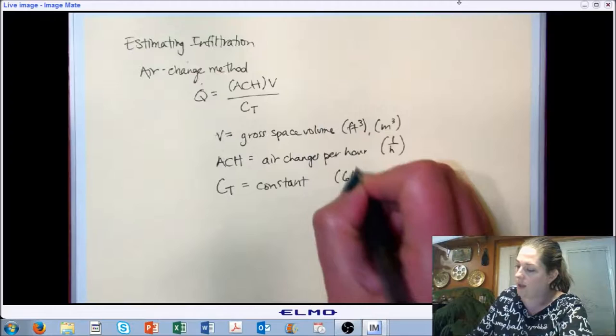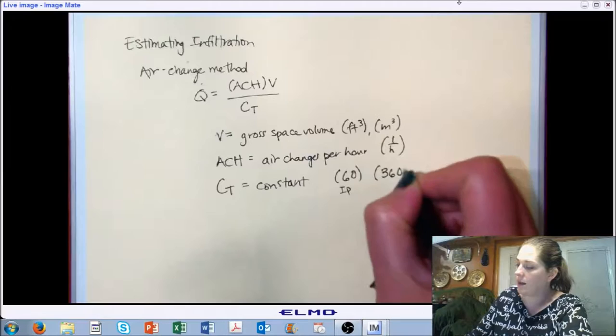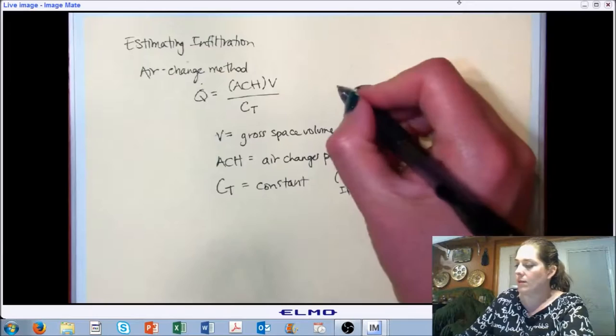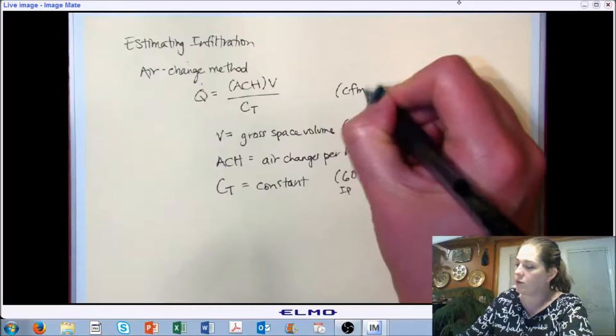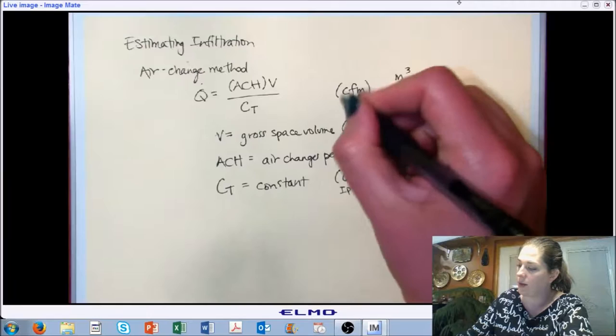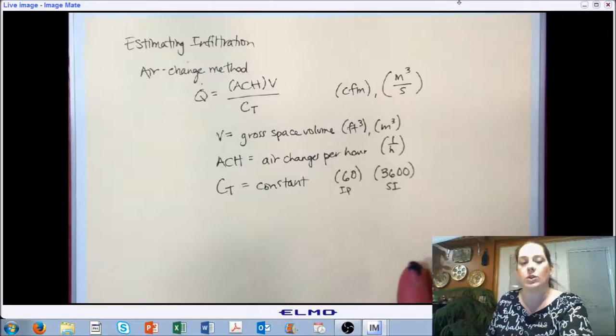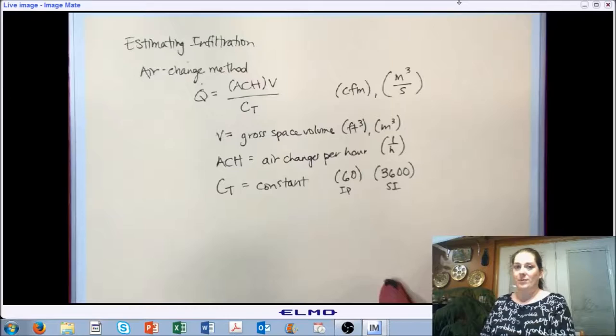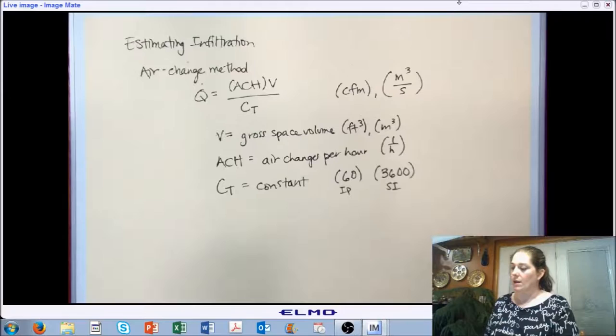If we are working in IP, that constant is 60. If we are working in SI, that constant is 3600. The units on Q, our flow rate — our estimate for infiltration — are in volumetric flow rates. For IP, we're at CFM, and for SI, we're in meters cubed per second. And it's that simple. That's the air change method.